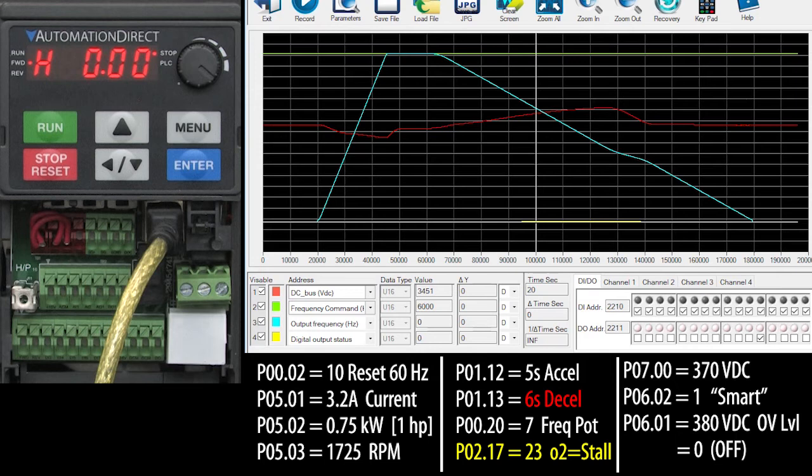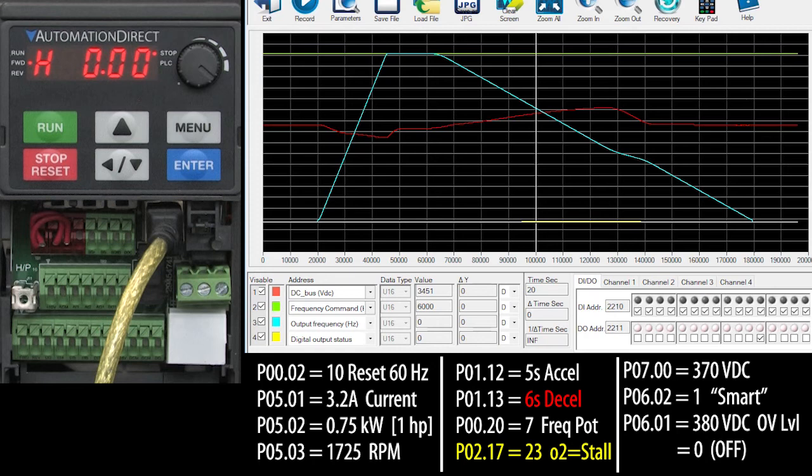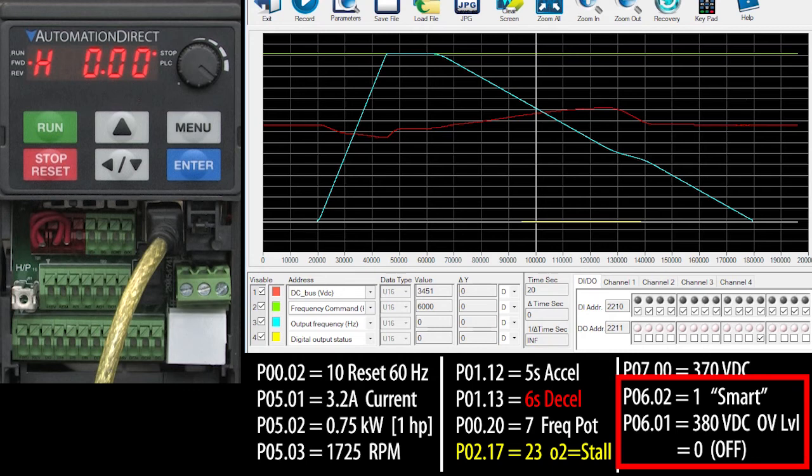But if my load changes, I'll have to go back and change that manually myself. The automatic stall prevention methods adapt the deceleration to whatever load you have so you don't have to mess with it and waste time trying to figure out what the right deceleration is. So it's usually a good idea to leave automatic stall prevention enabled.